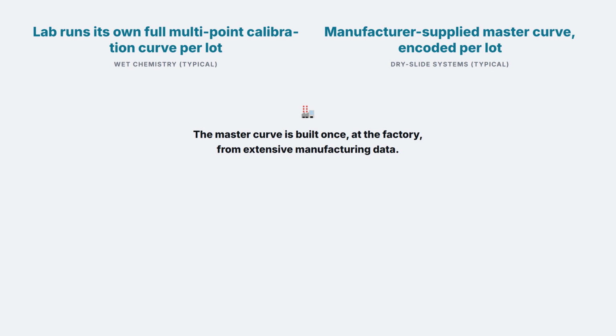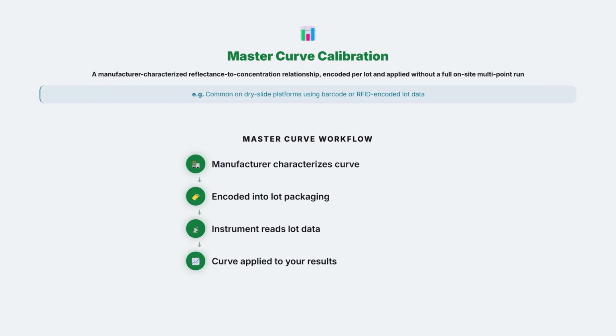The master curve concept, precisely: the manufacturer characterizes the full reflectance to concentration relationship for a given reagent formulation using extensive internal calibration data across many production lots, encodes that relationship into the slide packaging or instrument software, and your instrument then applies that pre-built curve directly to your slide lot. No full multi-point run required on your end.